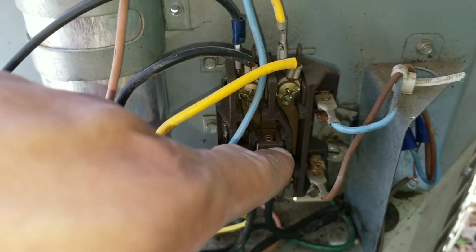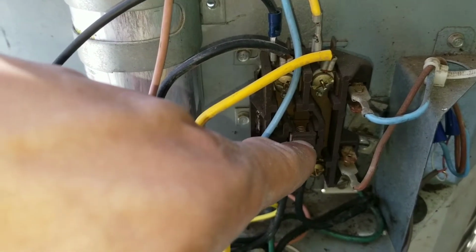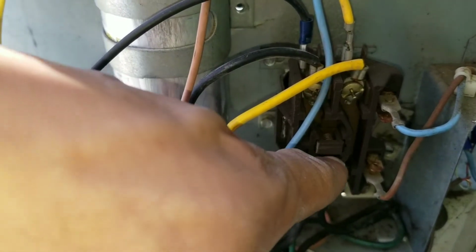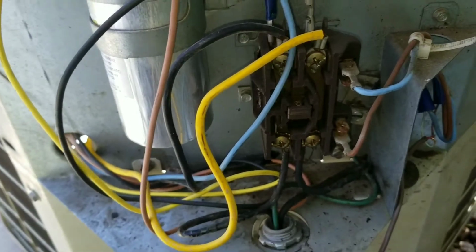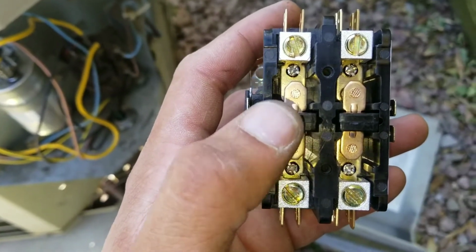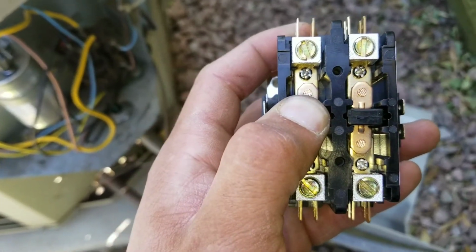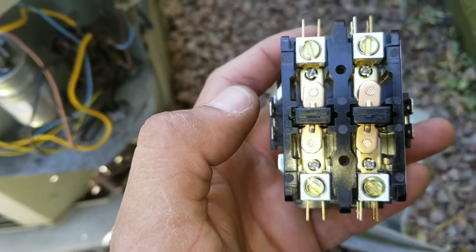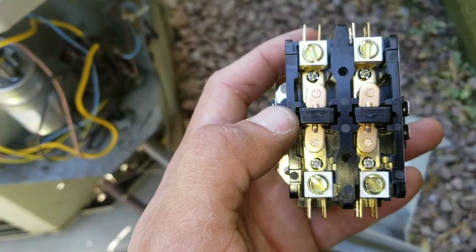And so right now, even though my thermostat is on the off and auto position, this should not be engaged. It should actually be depressed. So right now, we're going to start working on replacing this contactor. Here, this is the contactor replacement. And you can see here, when you push it in, it turns on when the signal is sent. And then when it's supposed to shut off, it should pop back up towards you. So right now we're going to replace this contactor in this condensing unit.